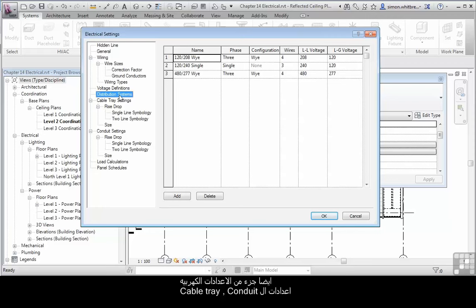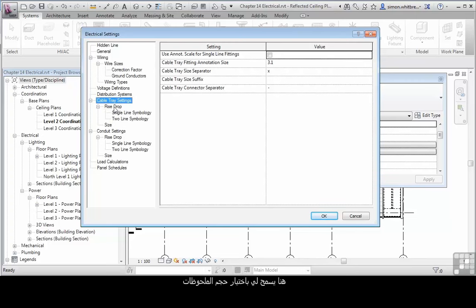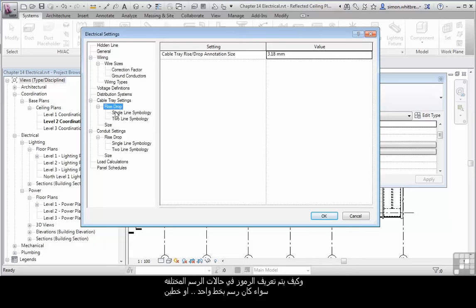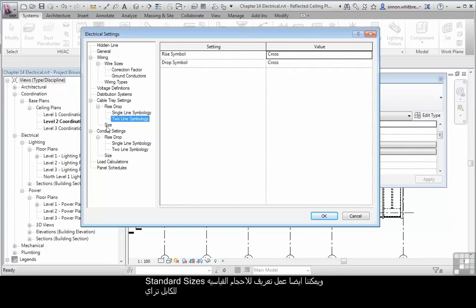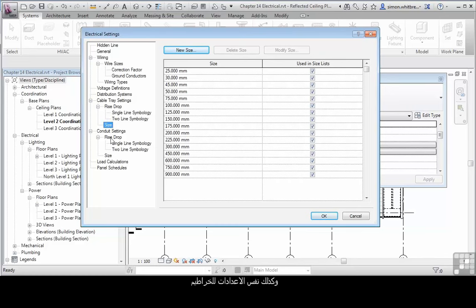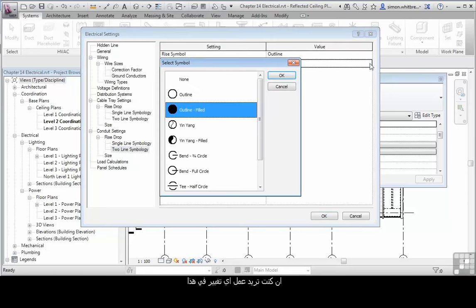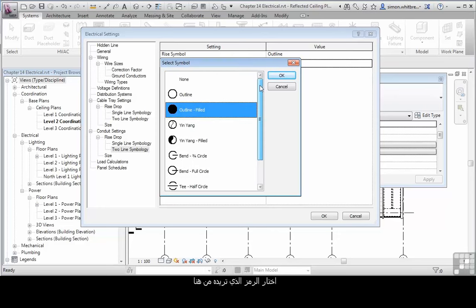Also as part of the electrical settings are the cable tray and conduit settings. These allow us to define the sizes of annotation display and how we define single line and two line symbology for our cable trays and for the conduits. We can also define the standard sizes that we're going to use for cable tray and we have similar settings for conduits. If you want to change any of these, select an appropriate symbol from the dialog box.